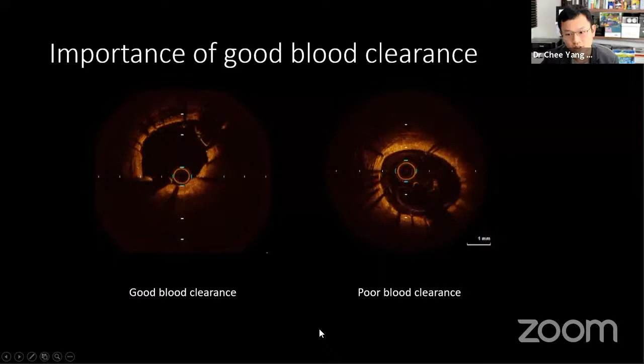Just a quick point about this, because the fellows always ask me in the lab. The OCT catheter on angio has 3 dots. There's a distal dot here that corresponds to the distal catheter tip. There's a middle dot. This is where the camera is, or where the lens is. You can see that for OCT, there's a longer distance between the distal catheter tip and the camera as compared to most IVUS systems. It's a little bit more dead space, so sometimes you can't reach very distal or very far down into the vessel. And this proximal dot indicates a length of about 54 millimeters between the middle and the more proximal dot.